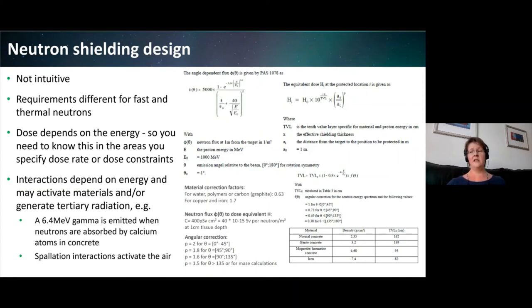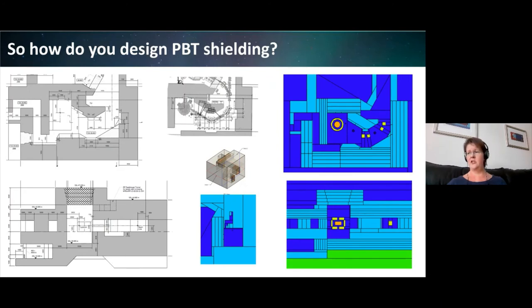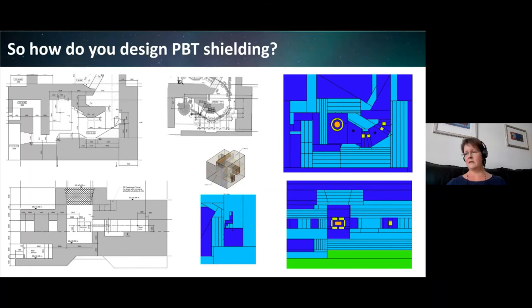In my experience, the question of how much shielding is needed is often approached from both directions — either 'I've got this much space, can I fit a proton beam therapy facility in?' — and the answer is often not really, but we'll try. So how do you design proton beam therapy facilities? You build and run a Monte Carlo simulation. The Monte Carlo input details the radiation source — in this case the collimated proton beam — and includes a geometrically accurate physical model of the facility, including concrete structures and large items like accelerator magnets, gantry counterweights, and bending magnets that could affect the neutron and proton scatter field. The Monte Carlo output contains information required to estimate dose rates or calculate the level of activation inside and outside the facility, and also allows you to assess scatter through penetrations, including large empty ones like the magnetic quench pipes in the accelerator.